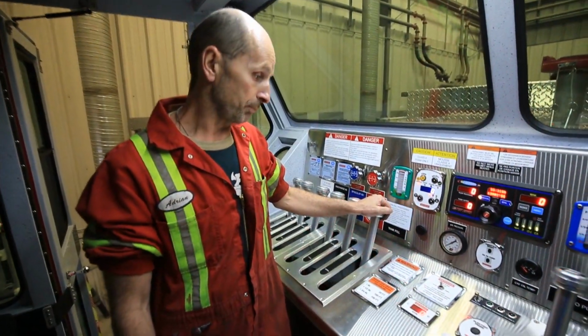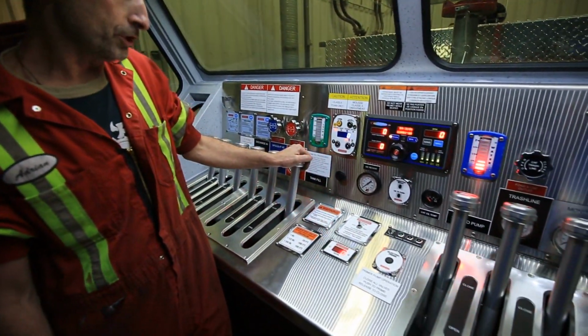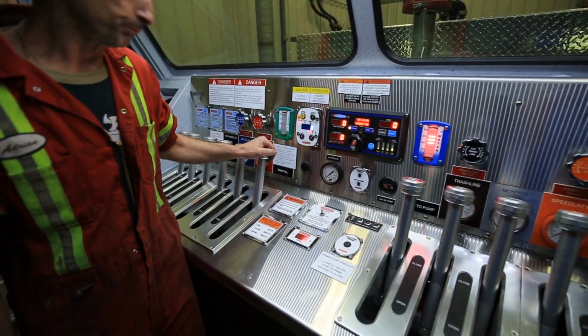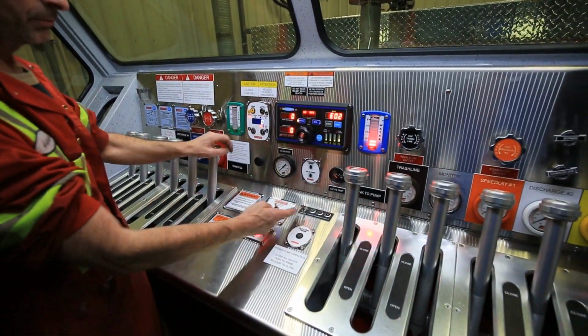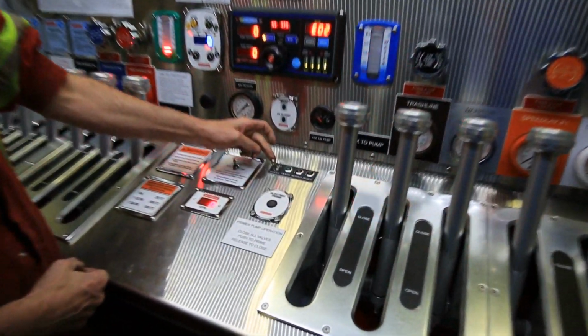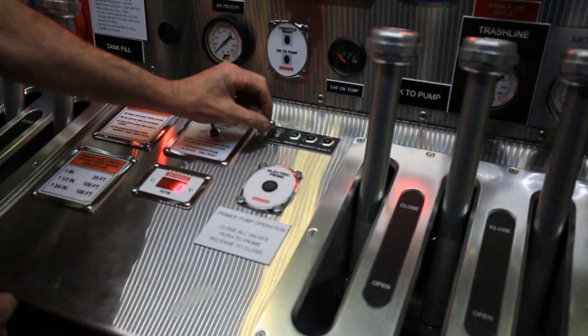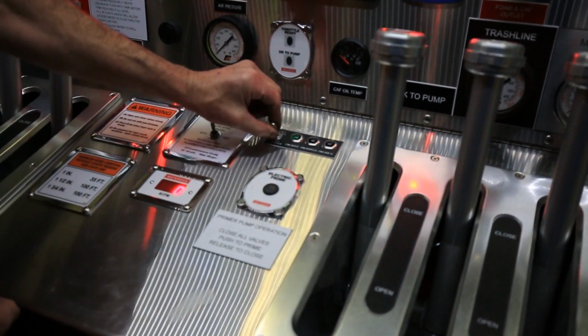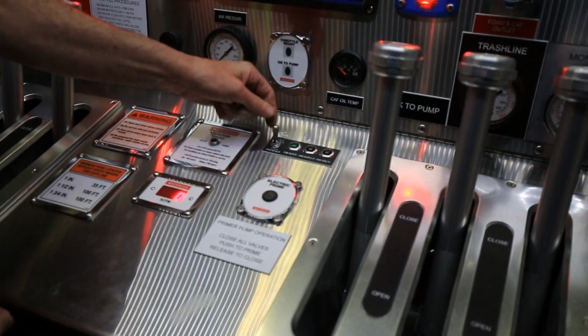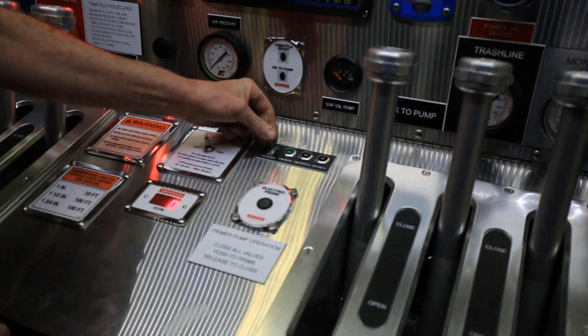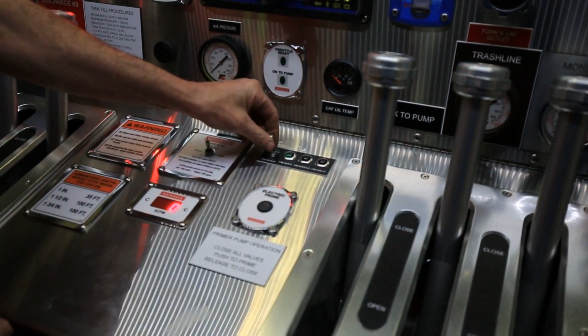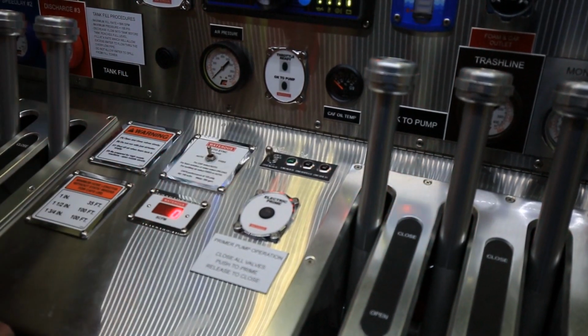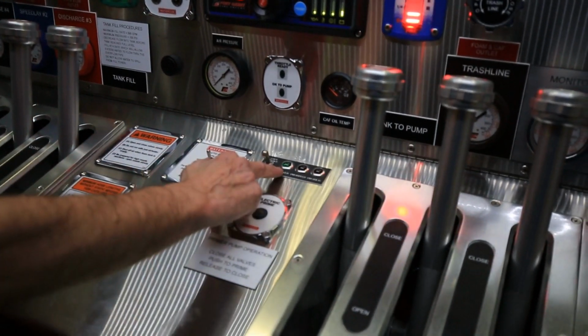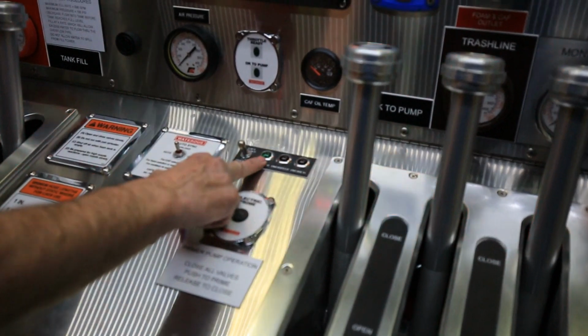Inside the pump house, on the pump panel, we have 2 switches and several lights and gauges. First of all, the main switch for the CAF system is a toggle switch. It has a small safety on it and has to be lifted up to engage. So lift and push forward to engage the pump, and lift and pull back to disengage. When it's engaged, the green light will come on.